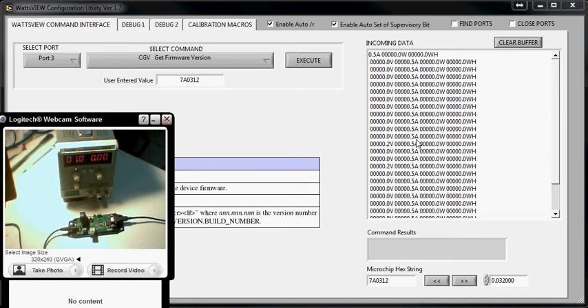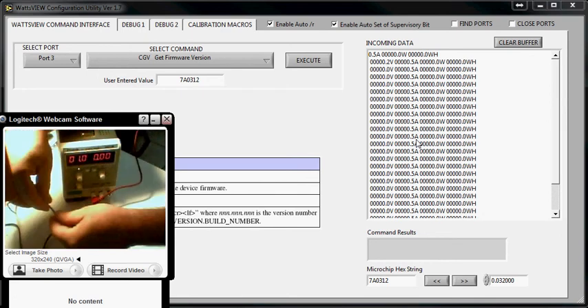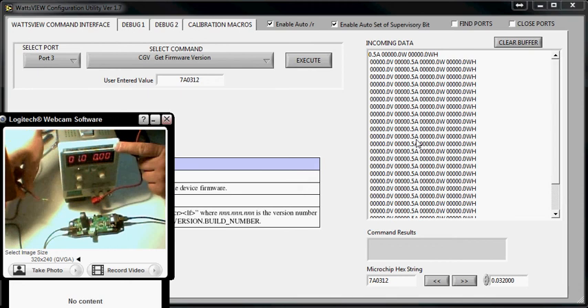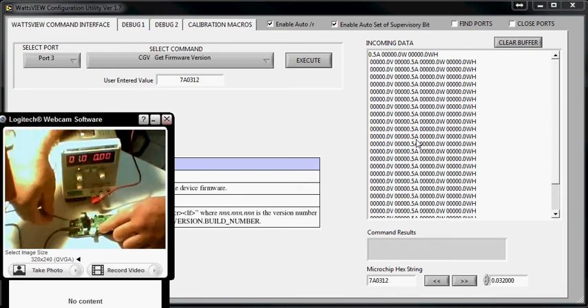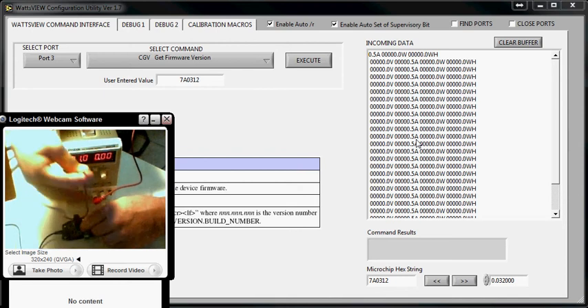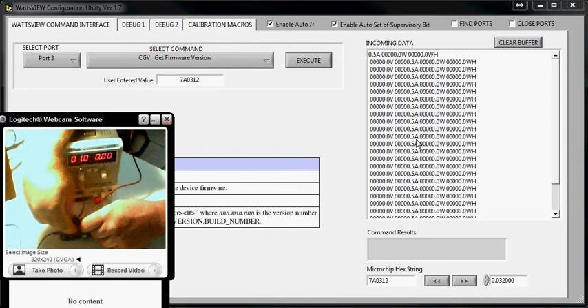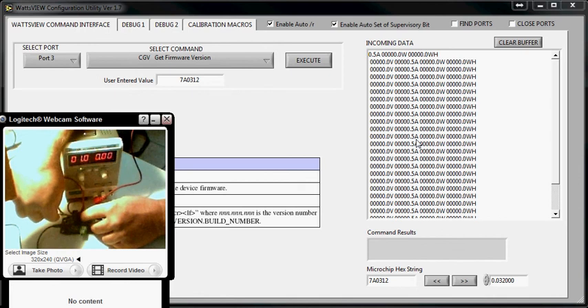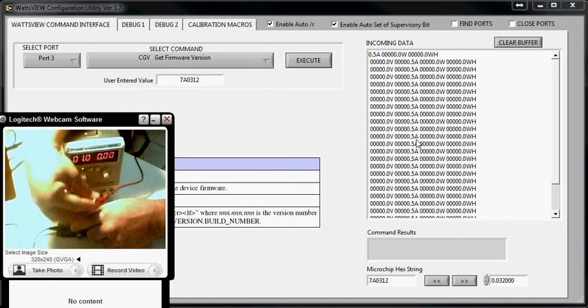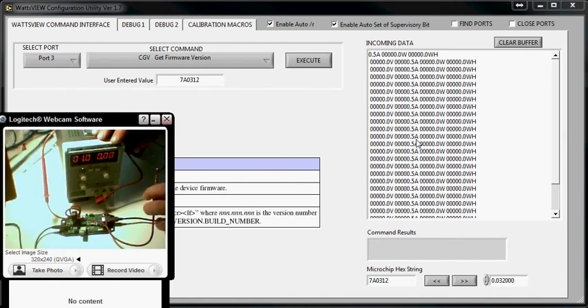So in this case, I'm just going to use this wire right here, plug it into the positive terminal, and to get more current simulated than 3 amps, because this power supply is an inexpensive power supply, it can only do 3 amps, we can loop this wire through the sensor once, twice, and a third time. So now 3 amps out of the power supply will show up as 9 amps on the sensor.